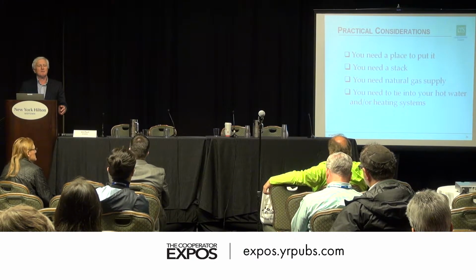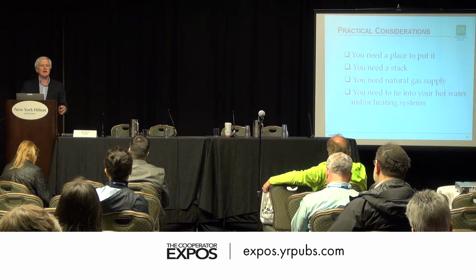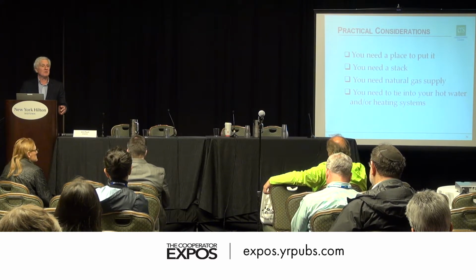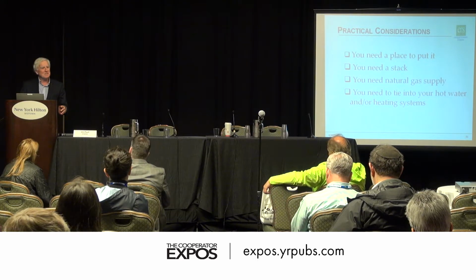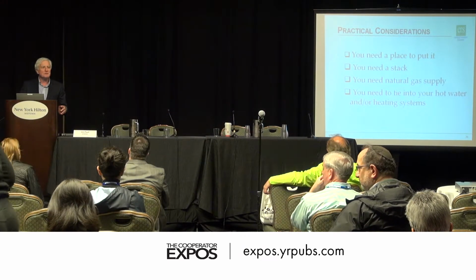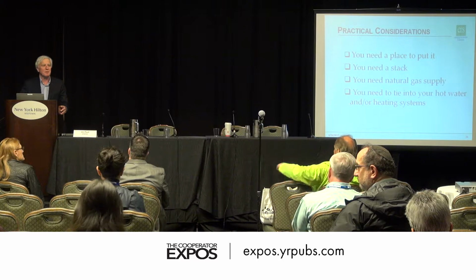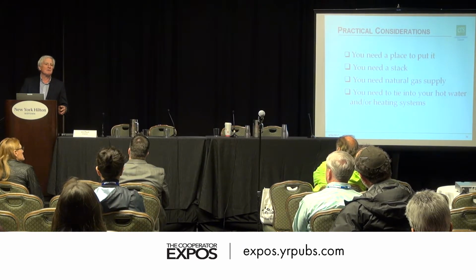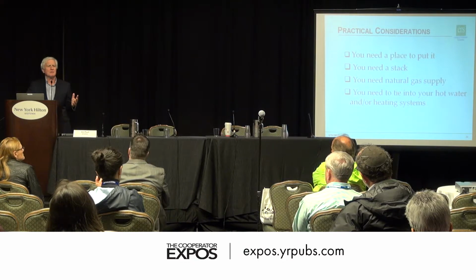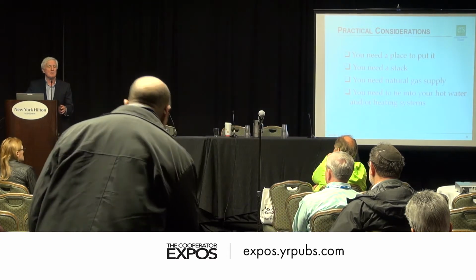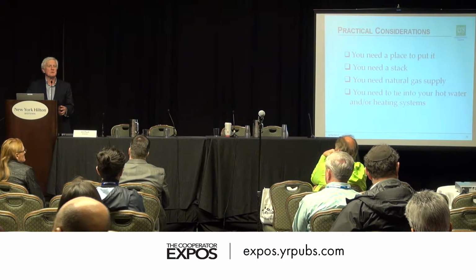For those of you with Con Ed steam, it's a bit more of a challenge, because you don't have a boiler room and you also don't have a stack to tap into. That doesn't mean it's the end of the world, though, because you can get creative and find places to put the CHP system - outside, or on the roof. Sometimes that requires a bit more capital cost, but it doesn't mean you can't do it. For buildings that already have boilers, it's usually a lot easier to find a place. These units aren't big, they're fairly small systems, and very often you want multiple units for redundancy and for maintenance downtime. So they can fit into some pretty modest spaces.